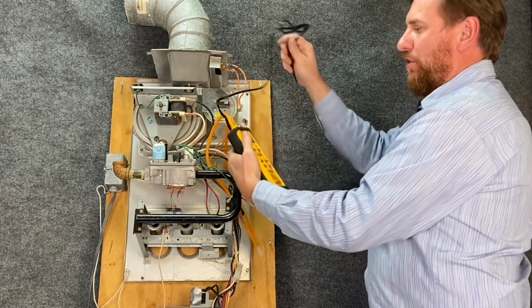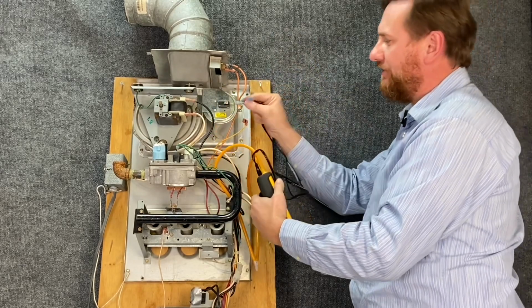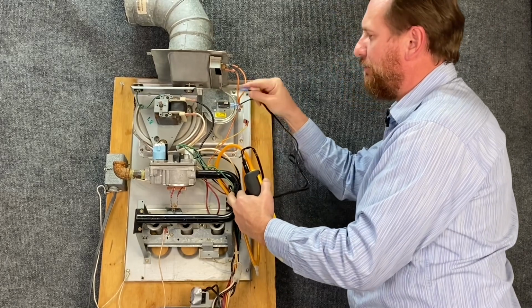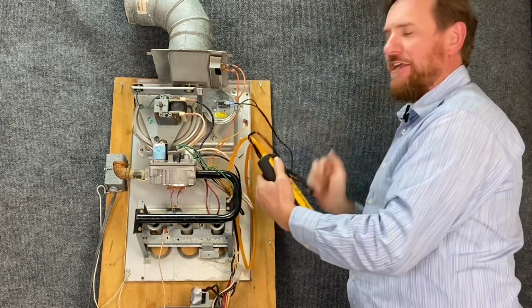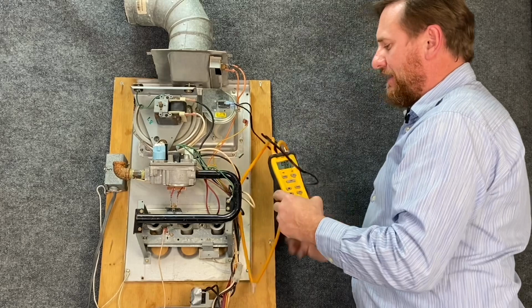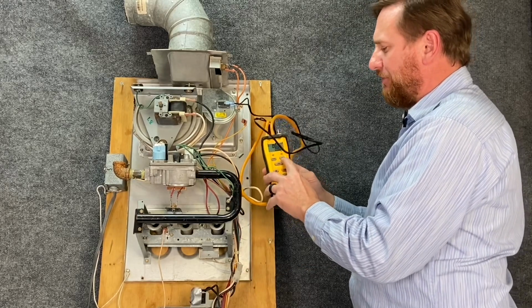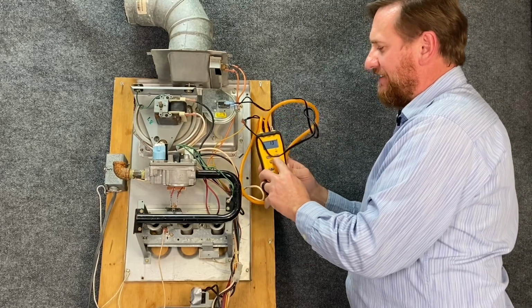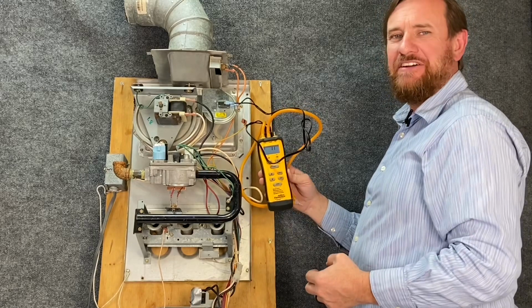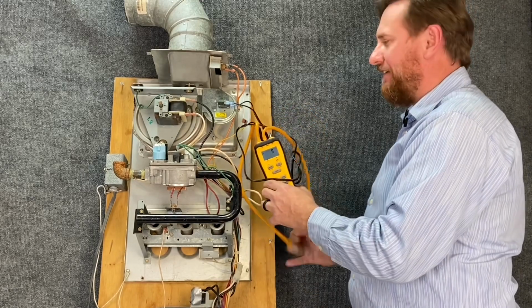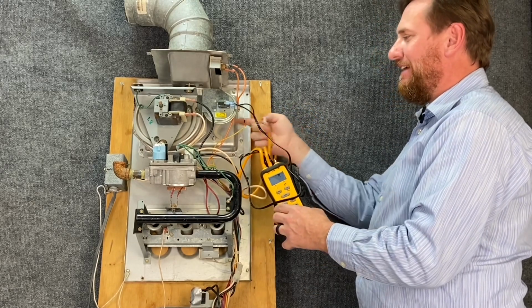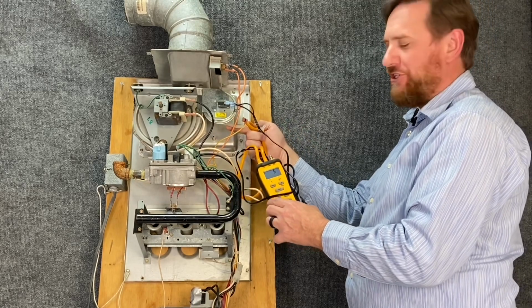This cord just has 2 plugs. We plug one into one side of our pressure switch and one into the other side. Now what I'm going to do is turn the pump on for test mode. So I press test. It's going to do a 13-second countdown. At the end of that countdown, I'm going to then hook up the T to my vacuum pressure switch.